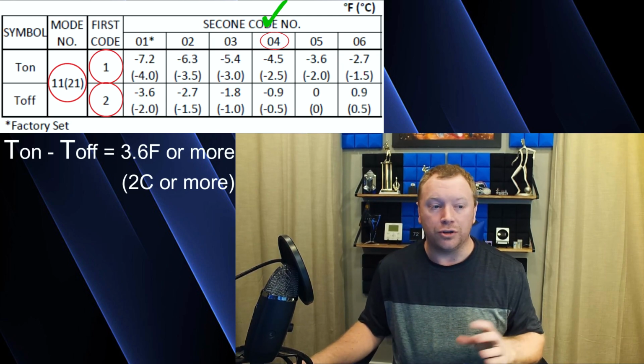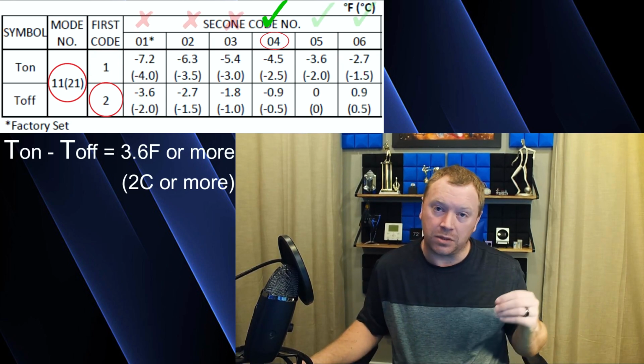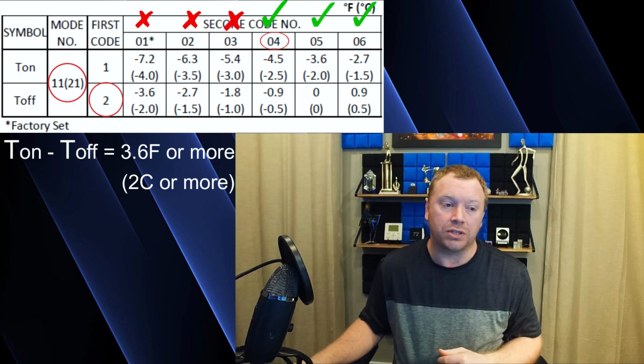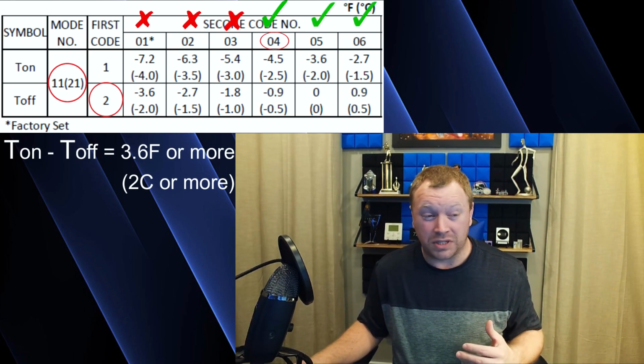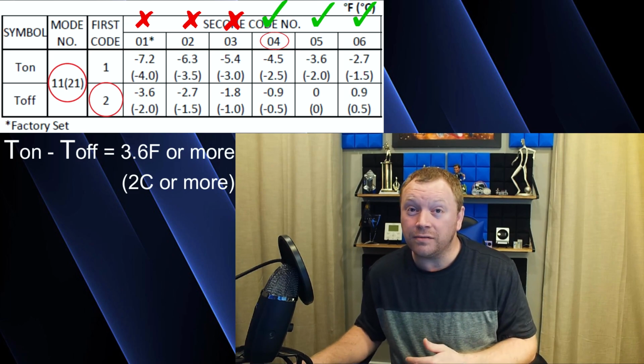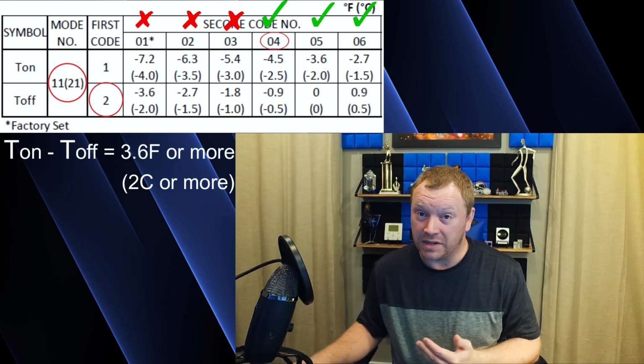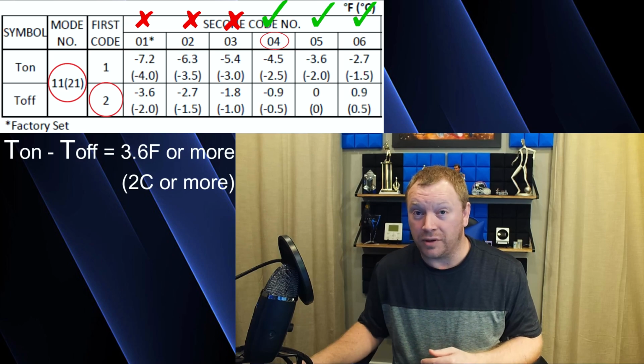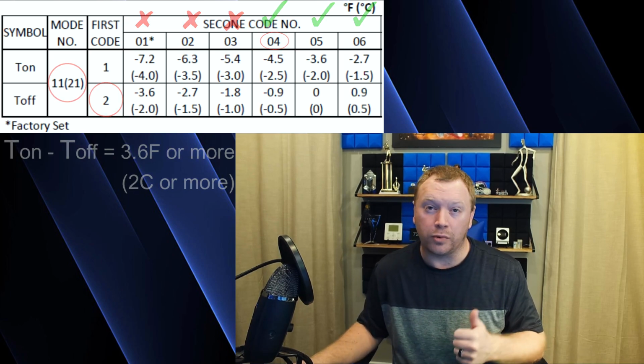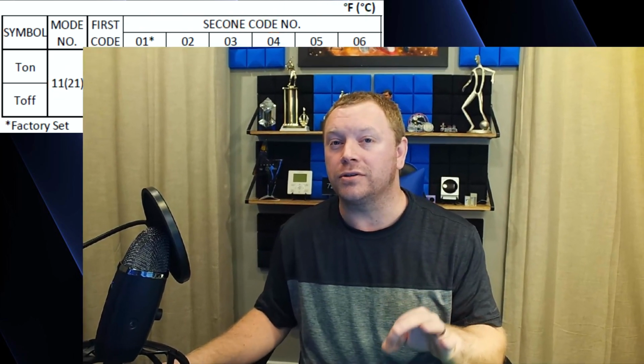And if you want, you can go beyond that. It just has to be at least 3.6 degrees. So if I wanted to pick mode 21 setting 2-05, well, 4.5 minus 0 degree drop from set point is 4.5, which is greater than 3.6, so you're good to go. Just make sure it's at least 3.6. And those are the 3 settings, technically 4 settings, that you will have to make sure to set if you have an FXTQ air handler with a strip heater added.